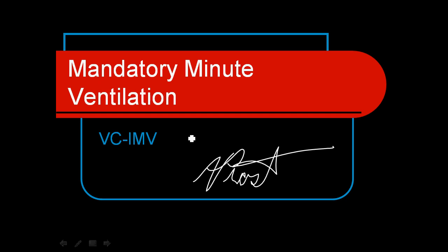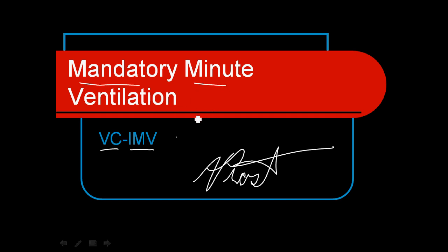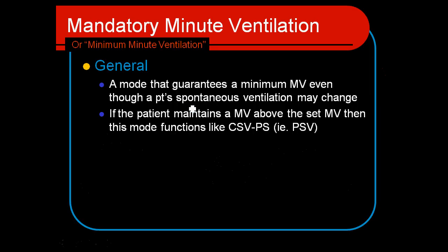Mandatory minute ventilation is a rather unique mode in that it uses volume control and it's an intermittent mandatory ventilation, so it allows spontaneous breathing in and around those mandatory or assisted breaths. What's unique is that it guarantees a specific mandatory minute ventilation and yet allows the patient to spontaneously breathe around that.